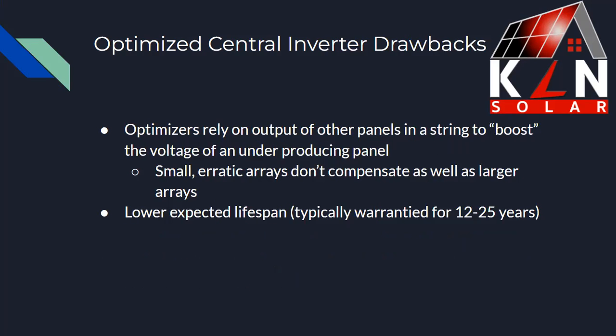Of course, optimized central inverters do have drawbacks. Optimizers rely on the output of other panels in the string to boost the voltage of an underproducing panel. This works 99% of the time, but if you've got small erratic arrays — two panels here, two there, two there all over the place on complicated roofs — they don't compensate as well as a larger array with multiple panels in a row all facing the same orientation. Also, there's a lower expected lifespan, since the inverter is processing the whole system's production, generating more heat and wear and tear. Typically they're warrantied from 12 to 25 years from the manufacturer.